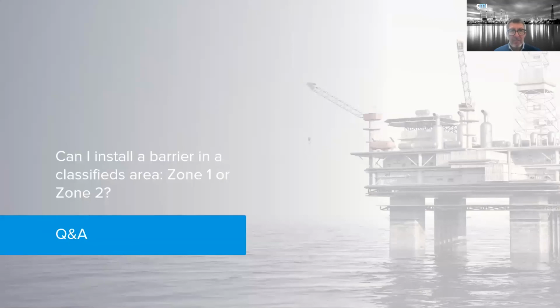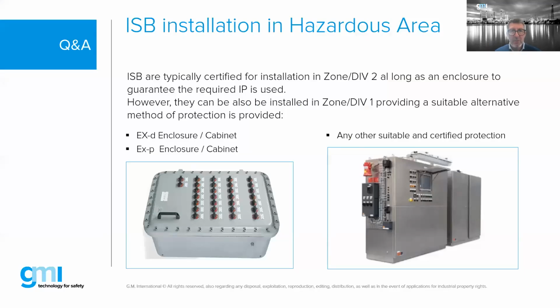You answered this already through the webinar. Can I install a barrier in a classified area? Yes, you can, but you must use a proper enclosure or use a barrier which is designed for installation in the classified area, such as GMI. You can install in Division 2, of course, providing an IP54 enclosure, some kind of cabinet.